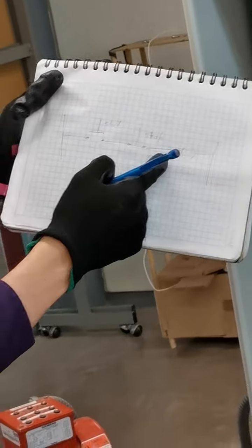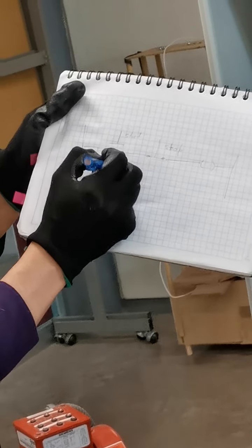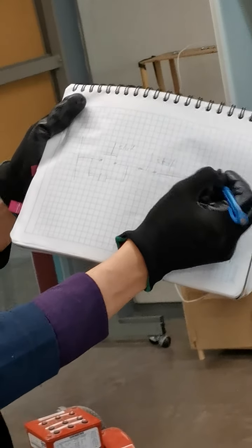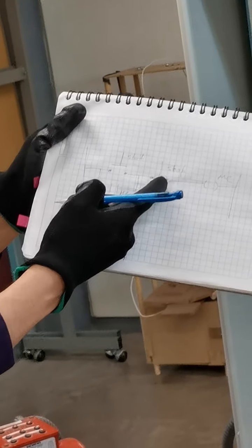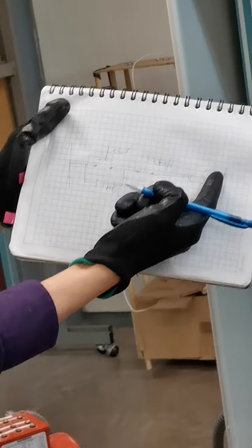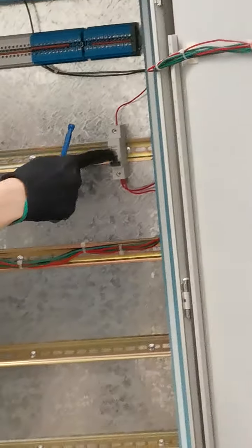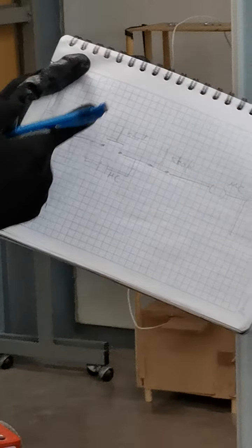And in order to latch it, you have over here a contact of this motor coil. This one over here is going to be the motor coil. You remember that this one is a latch. So you have your start, you have your stop, normally open, normally closed, your coil, and then a contact of this coil. This configuration is the one that we have over here. So this thermomagnetic switch is around here, connecting this section in order to energize all of your system.